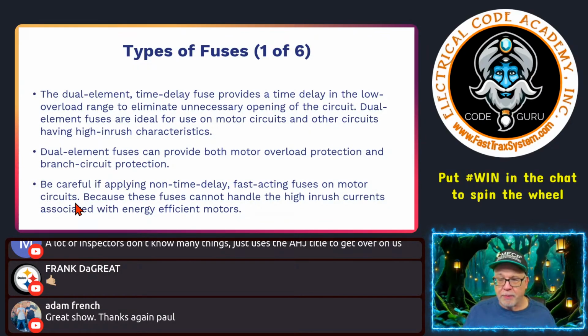Now, be careful if applying non-time delayed fuses. Fast acting fuses basically are just like the circuit breaker. They don't have any delay. You get to a certain level and they trip, okay, or they blow, okay? So be careful if you're using those on a motor, because these fuses cannot handle that high inrush, with the energy efficient motors. So again, be careful. And nobody in their right mind would use a non-time delay or a fast-acting fuse on an application that needs that inrush to be taken into consideration.